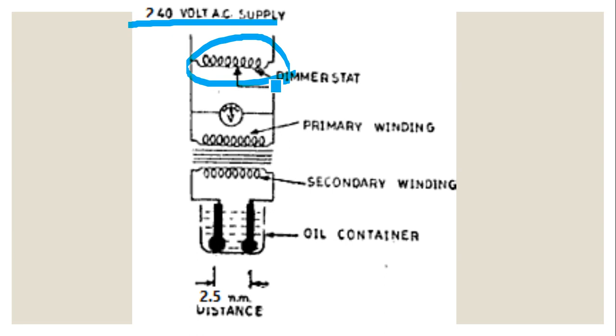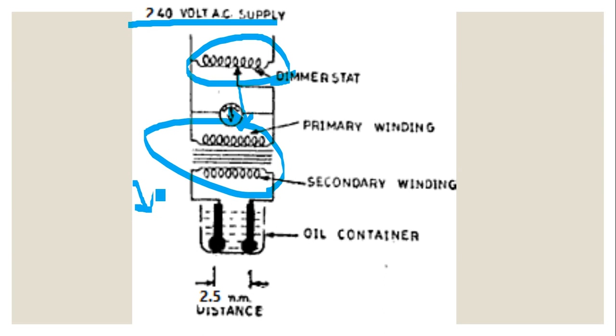This is the voltage variation device, also called auto transformer, dimmerstat, or variac. As we change the input voltage, this step-up transformer increases the voltage, generally rated from 0 voltage up to 100 kV. When the high voltage is available here, there will be a spark between the electrodes, and that is known as the breakdown voltage of the oil.